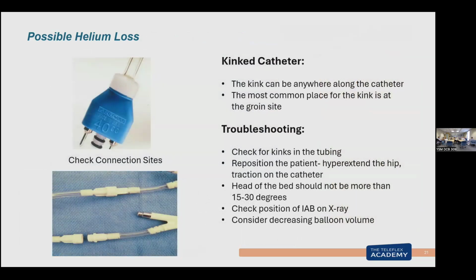The other places that you can have a possible helium loss could be the connector itself. This is rare, but if I have splits on my little O-rings, there's your helium loss. I'm going to have to change out this connector. And then making sure that my connection is tight here.